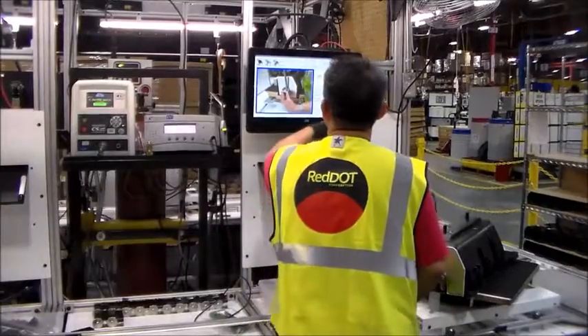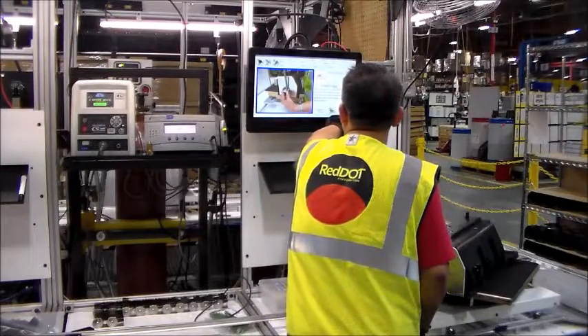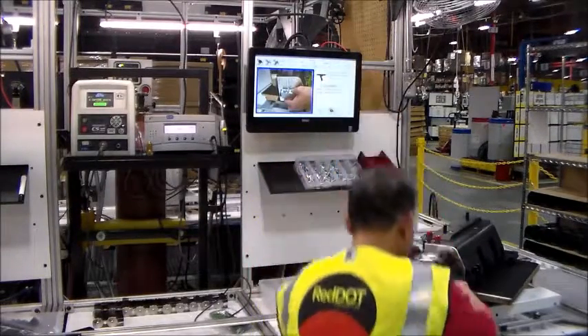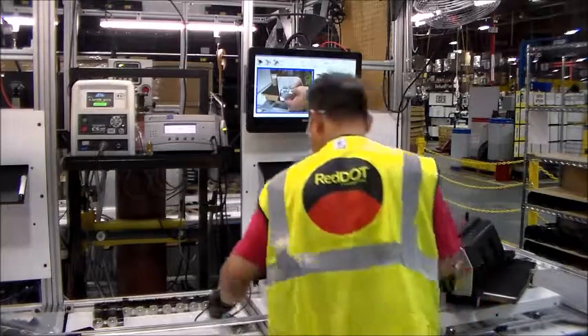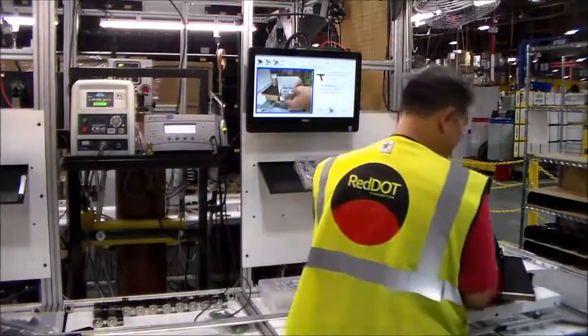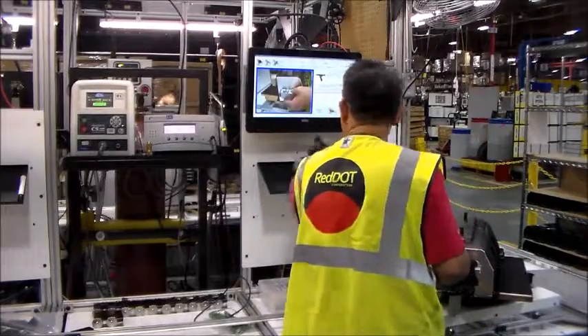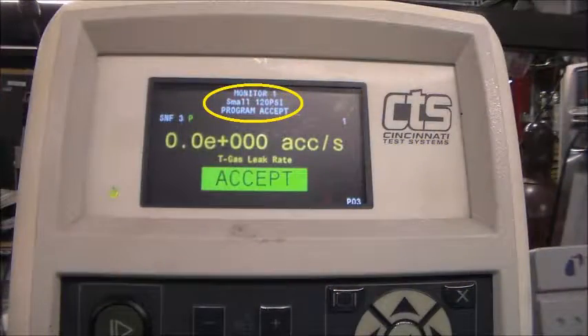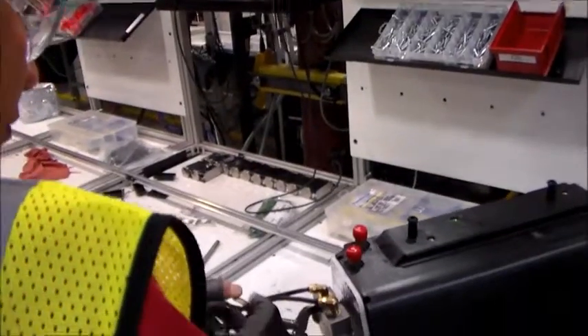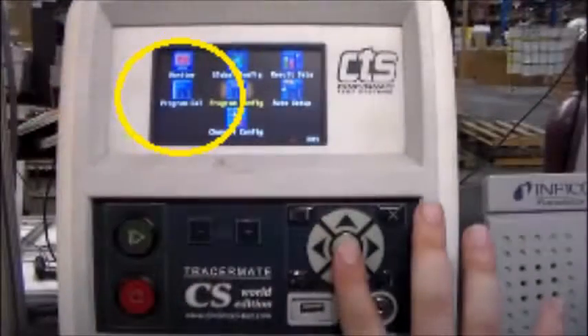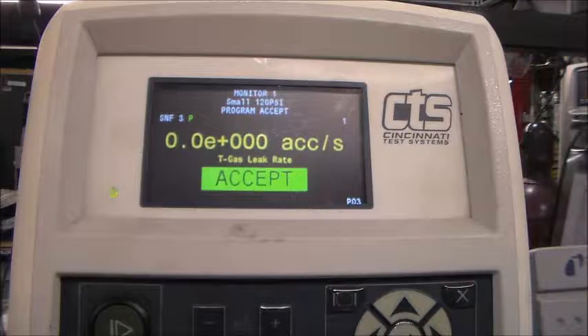In addition to the daily self-test, the tracer mate must be auto-calibrated for the unit you are working on at the beginning of work every day, whenever you are starting a new run, or working on any part different from the one the tracer mate has been auto-calibrated for. Check to make sure the pressure is set correctly according to the corresponding method sheet or blueprint for that part. Start by connecting a known good part to the instrument. Press the menu button and scroll left to the Program Cal button and hit Enter to begin the test. The tracer mate will indicate whether the part has passed the test or not.